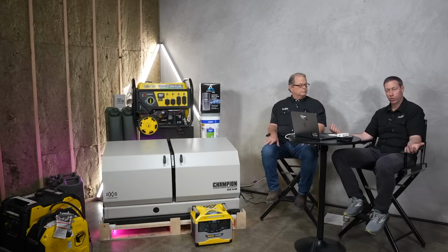So what you want to do is take that 1.6 and multiply it by how many hours you think you want enough storage for. If I'm going to run that thing for 2 weeks, I need to go: 24 hours times 14 times 1.6 - that's how much storage I need. And then you also need to think about, hey, if I ran it and didn't refill my tank, maybe I want a little bit more storage there. Those are the kind of calculations you're going to do.